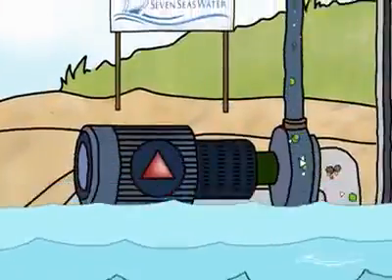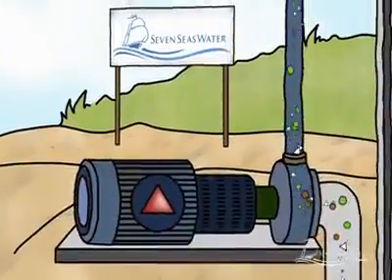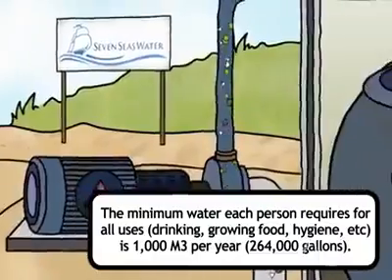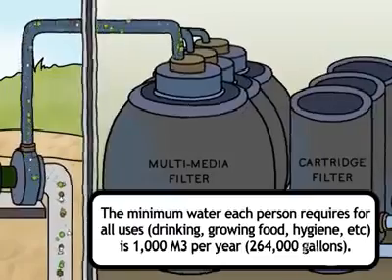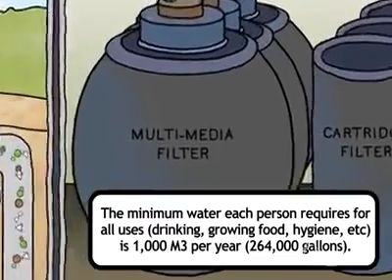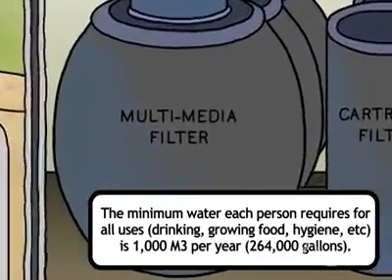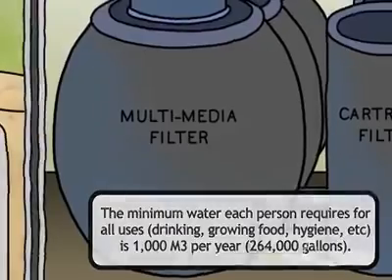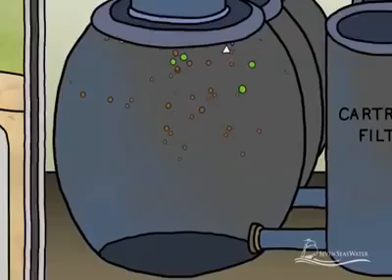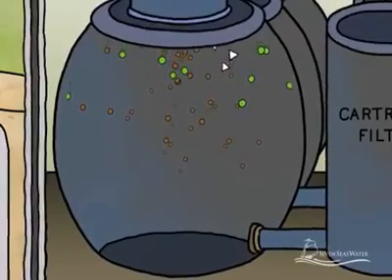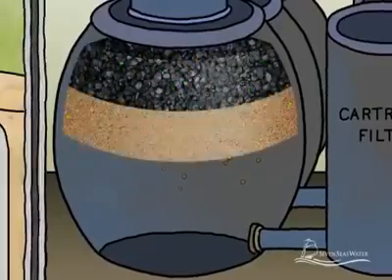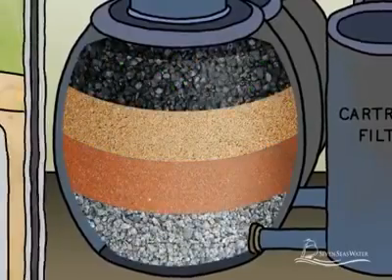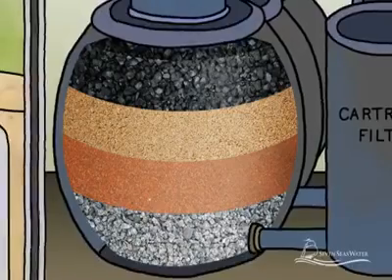To protect the reverse osmosis membranes from becoming clogged by solid particles that can be suspended in the seawater, the seawater is filtered before passing through the membranes. This is accomplished by using multimedia filters, which are tanks or vessels containing a series of layered granular materials. These materials can be anthracite, garnet, sand, pebbles, and/or gravel, which are assembled in layers.